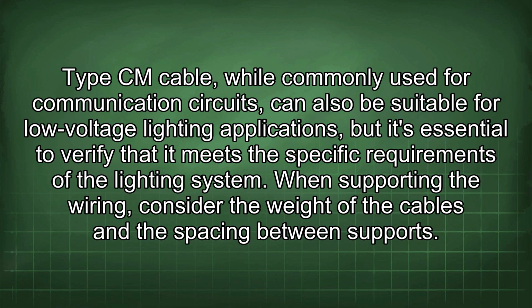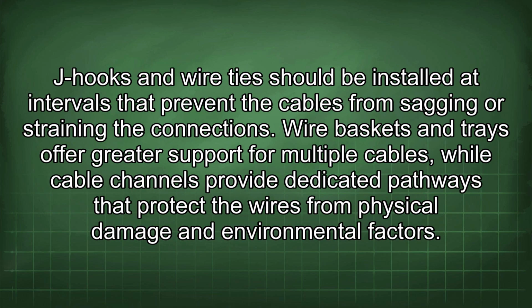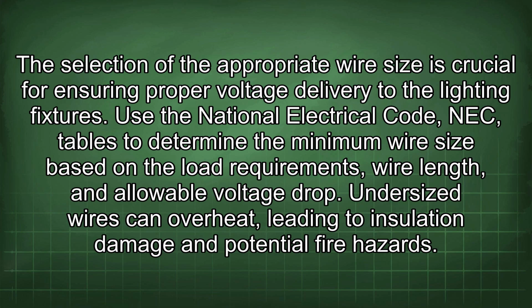When supporting the wiring, consider the weight of the cables and the spacing between supports. J-hooks and wire ties should be installed at intervals that prevent the cables from sagging or straining the connections. Wire baskets and trays offer greater support for multiple cables, while cable channels provide dedicated pathways that protect the wires from physical damage and environmental factors. The selection of the appropriate wire size is crucial for ensuring proper voltage delivery to the lighting fixtures. Use the National Electrical Code (NEC) tables to determine the minimum wire size based on the load requirements, wire length, and allowable voltage drop. Undersized wires can overheat, leading to insulation damage and potential fire hazards.